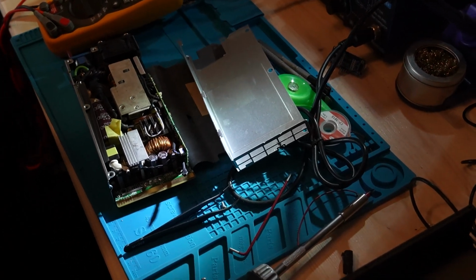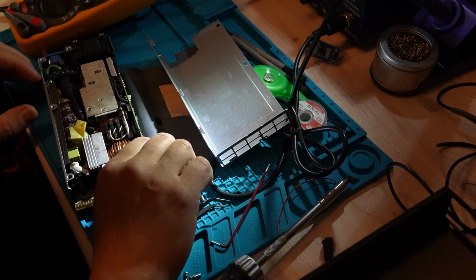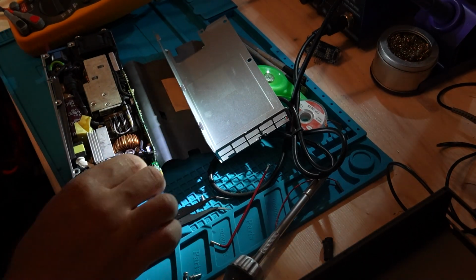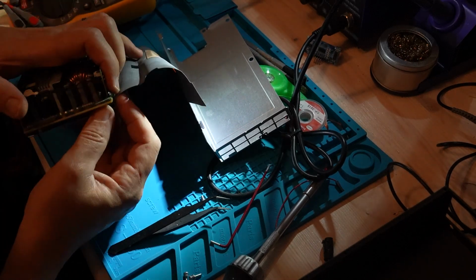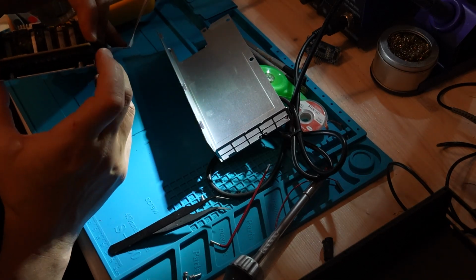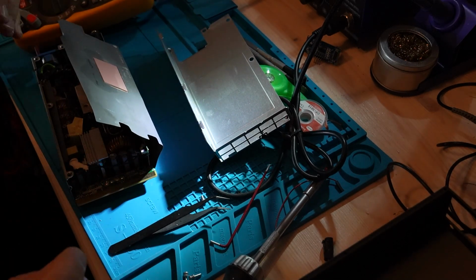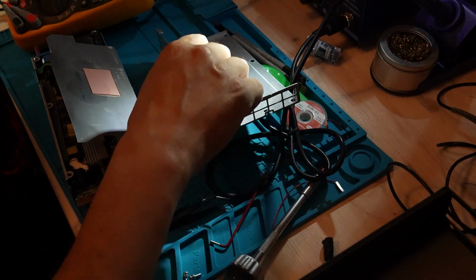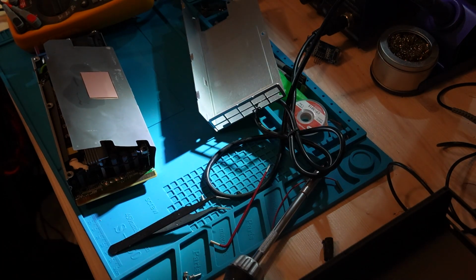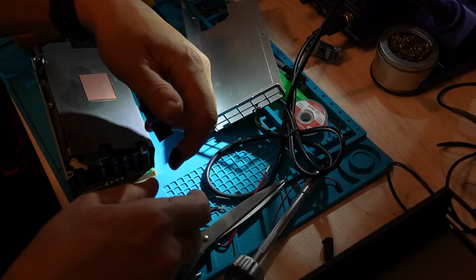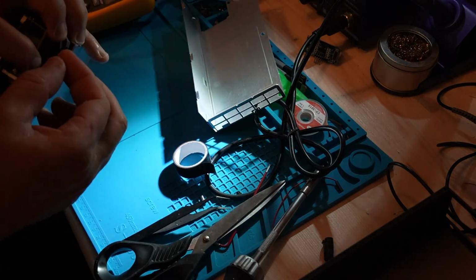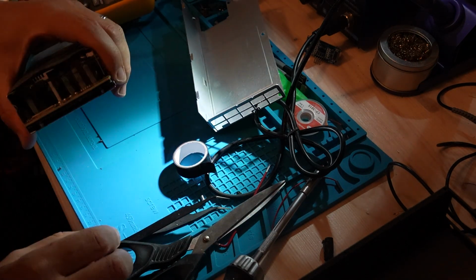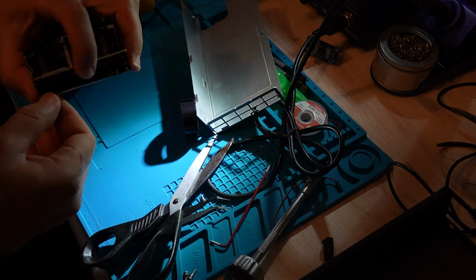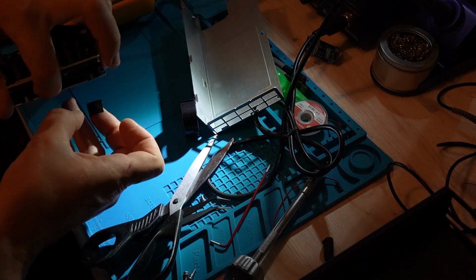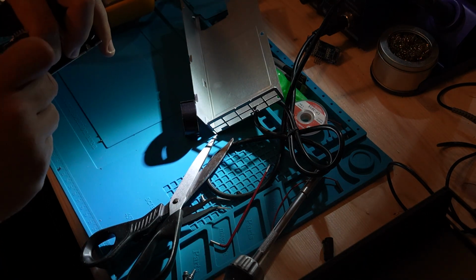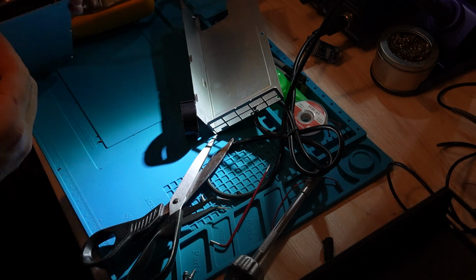When connecting two HP power supplies in series, you must isolate the ground negative pin of one of them from the chassis earth ground. What I mean by ground here is the negative output pin — it must not be connected to the PSU chassis ground internally. How to test: use a multimeter in continuity mode. Place one probe on the negative output pin and the other on the PSU chassis or ground pin. If you hear a beep, it means there is continuity and you need to isolate it.